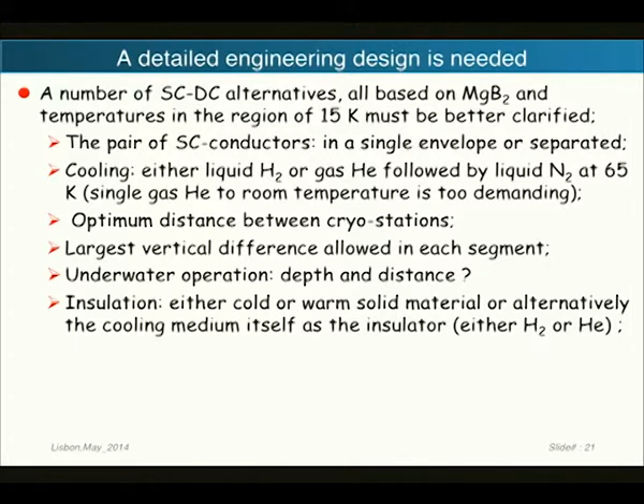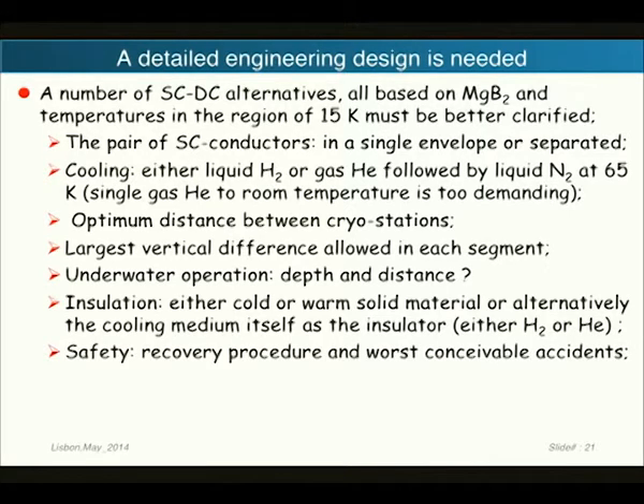Then the question is what you need—since the voltage will be lower, you can choose either cold or warm solid insulating material. Or perhaps the cooling medium itself could be the insulator. For instance, liquid hydrogen can be a practical insulator for this kind of voltage, and compressed helium can also be an insulator itself. So it can be either the gas itself or an extra insulator added.